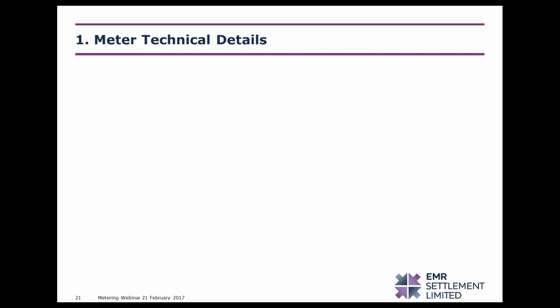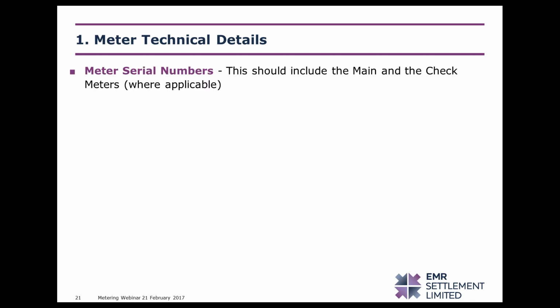Firstly, taking the meter technical details, this is related to Section C of Schedule 6, and it is about the configuration and setup of half-hourly meters. You must include all meters in this section. This will include main meters and check meters where they are applicable. The reason that check meters must be included is that should the main meter become faulty, data from the check meter will be used in the capacity market, and as such, the check meter is subject to the metering test.